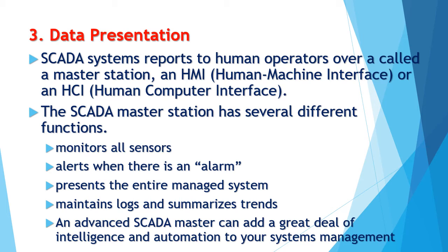The SCADA station has several different functions. First is to continuously monitor all sensors. Second, it alerts the operator when there is an alarm. Third, it presents a comprehensive view of the entire managed system. Fourth, it maintains report logs and summarizes historical trends. And lastly, an advanced SCADA Master can add a great deal of intelligence and automation to your system's management if properly programmed.